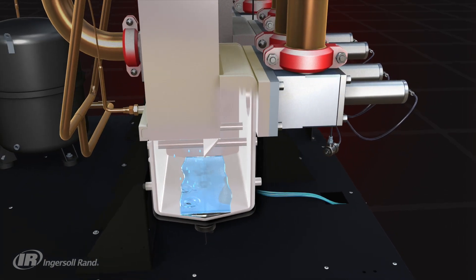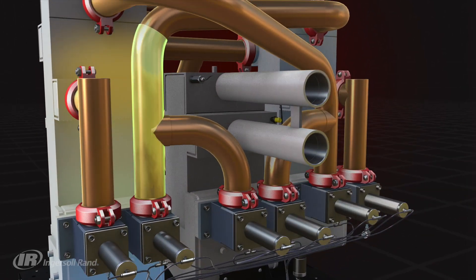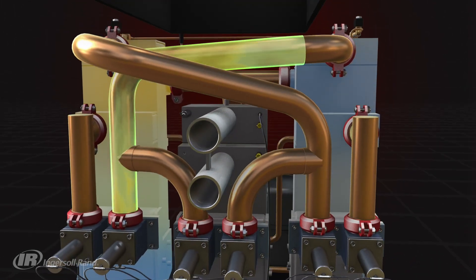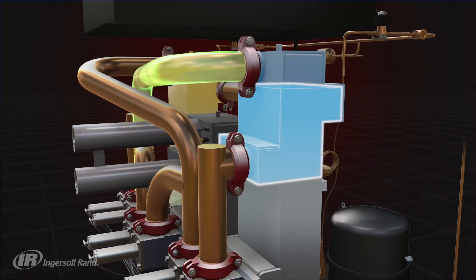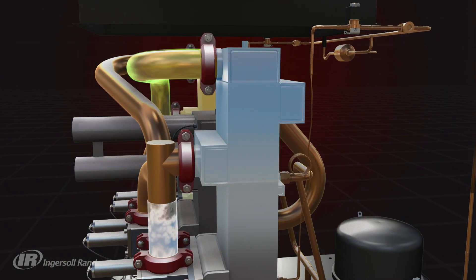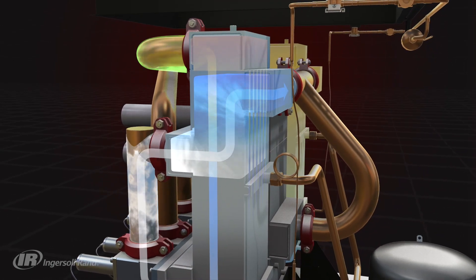The pre-dried air still contains some useful heat energy when it arrives at the active sub-freezing unit, and before entering the lower refrigerated sub-freezing chamber, it passes through an additional thermal exchange process where it partly reheats the freeze-dried air that has just exited the sub-freezing chamber.